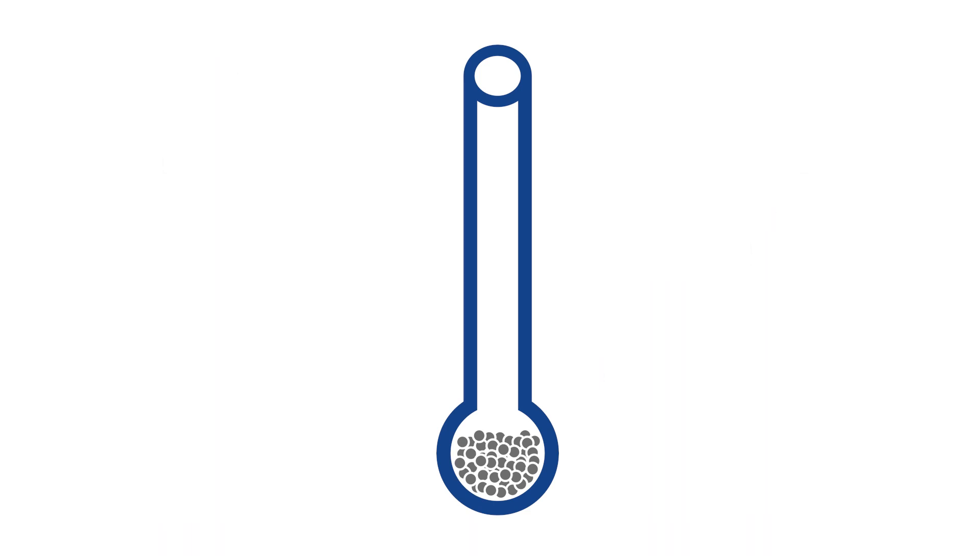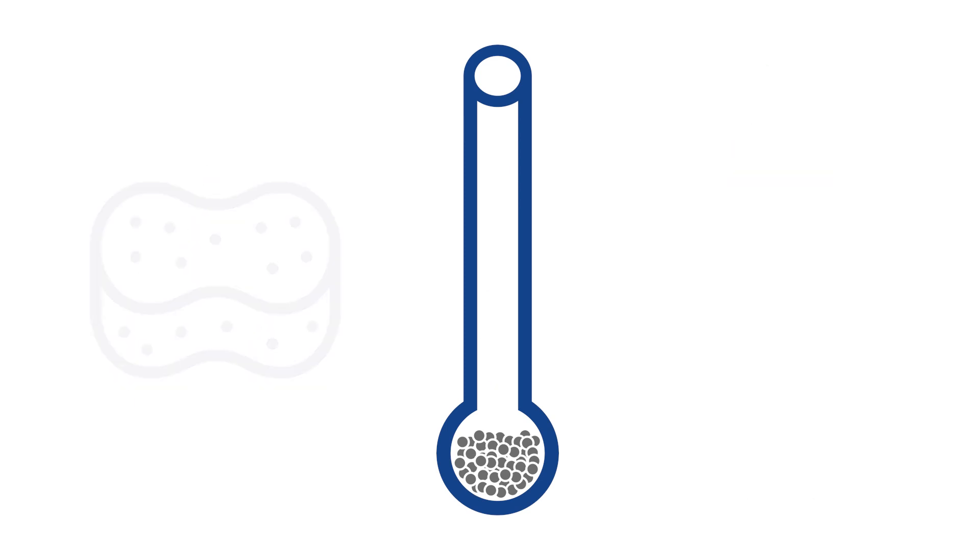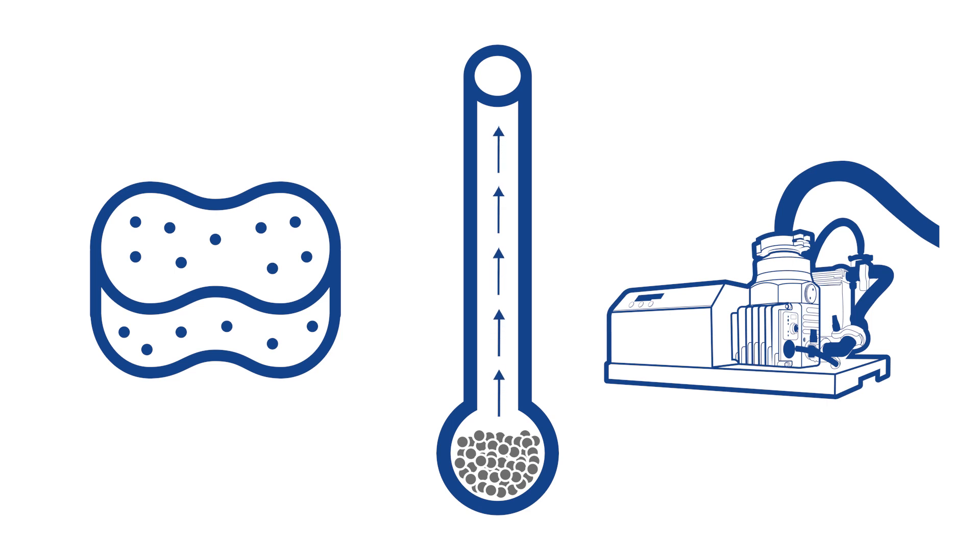When the material is known to have a high moisture content, flowing nitrogen can speed up the degas time, also known as a flow degas. When working with microporous samples, a high vacuum degas is preferred.